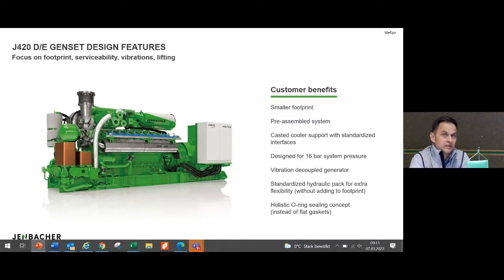So the customer benefits out of this new genset are the following. For sure, a smaller footprint, as said. We have now a pre-assembled system. All hydraulic integrations or connecting points to the customer interfaces are always in the same position. There is no change. Design protected or designed for 16 bar system pressure, so no need for any special release if you want to have 16 bars. So this is now our new standard. We have a vibration decoupled generator now.